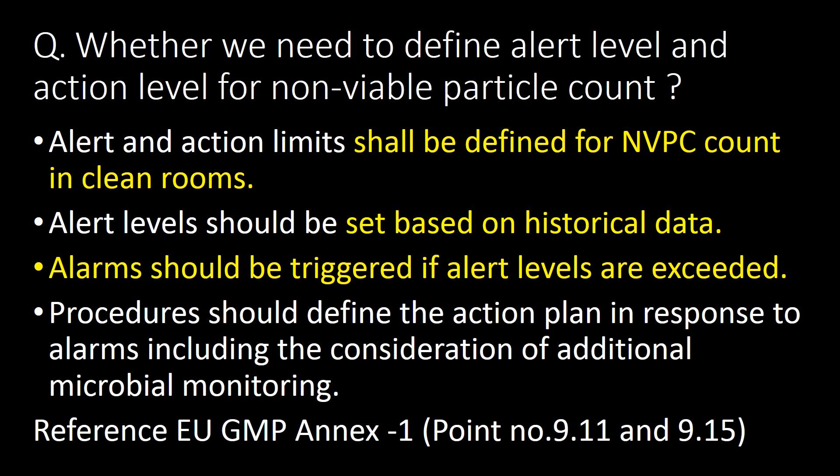Whether we need to define alert levels and action levels for non-viable particle count. The answer is yes. Alert and action limits shall be defined for NVPC count in clean rooms. Alert levels should be set based on historical data. Alarms should be triggered if alert levels are exceeded. Procedures should define the action plan in response to alarms, including consideration of additional microbial monitoring. Reference: EU GMP Annex 1, Point No. 9.11 and 9.15.